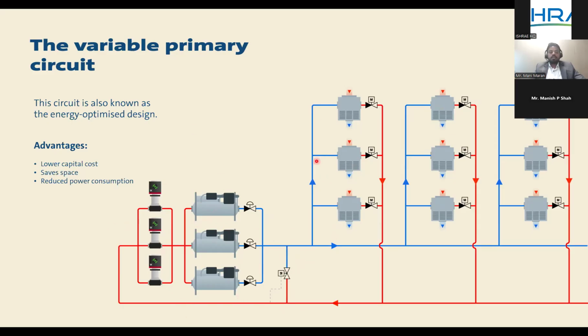But let's see the scenario where the balancing is not proper as per ISHRAE and 90.1. Let me put it this way: valve authority is a critical parameter which has to be considered during design. ISHRAE clearly defines that 30 to 40% of the entire friction of the system has to come from these valves.